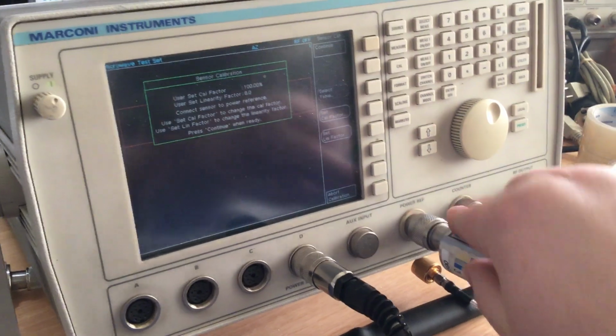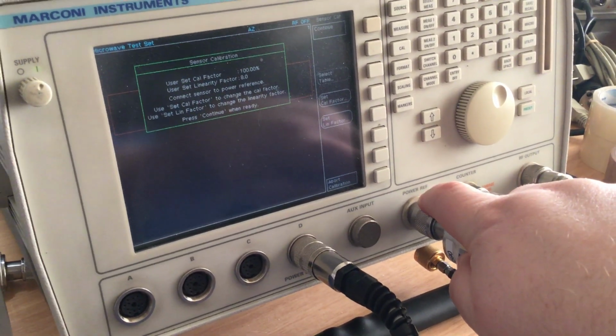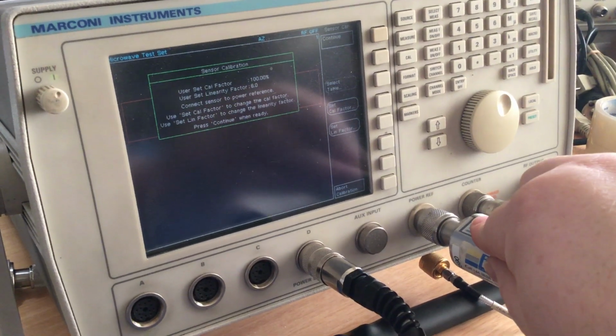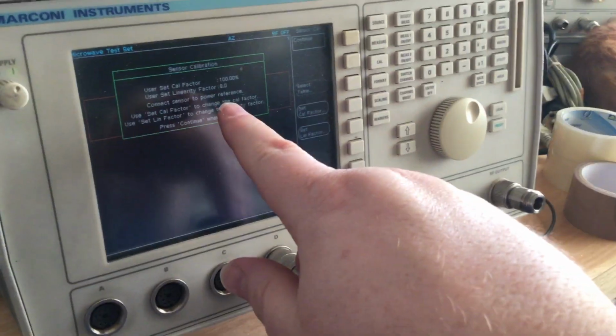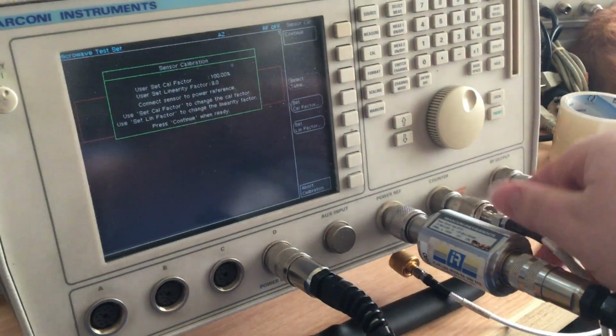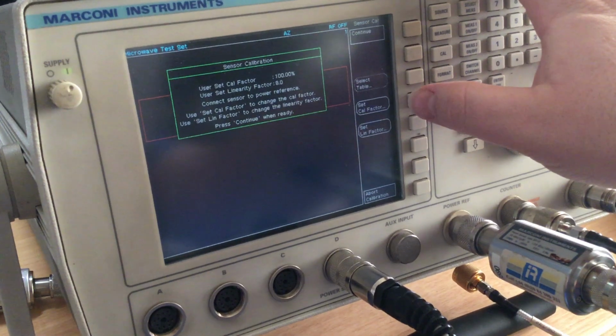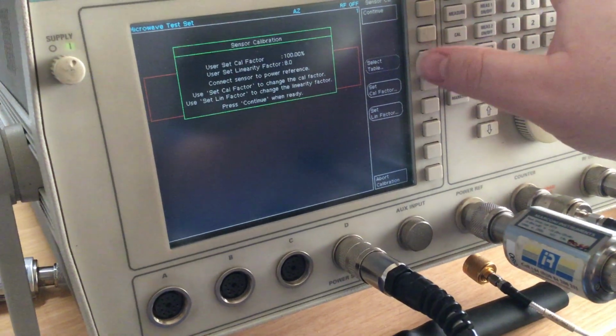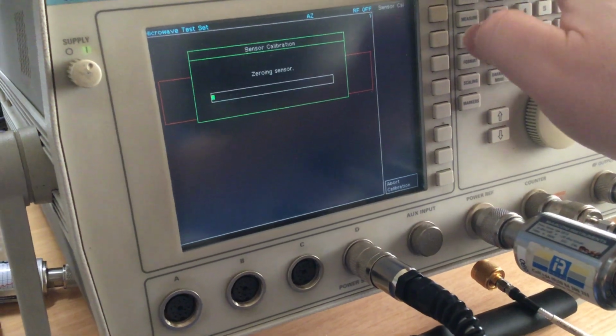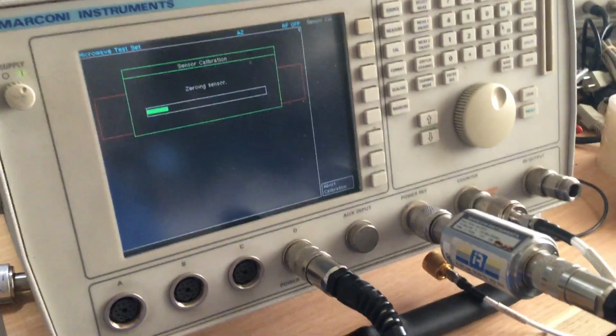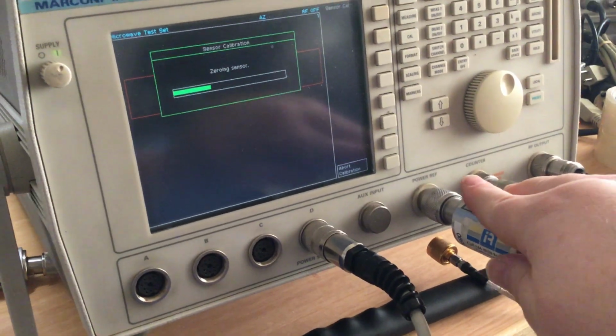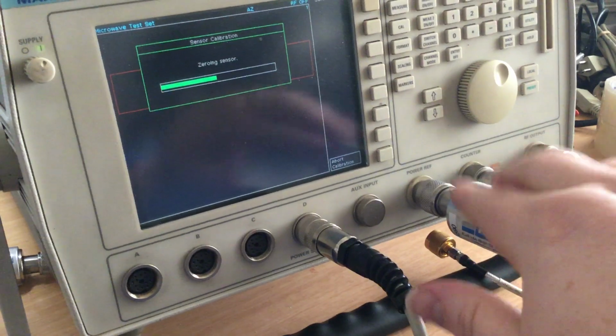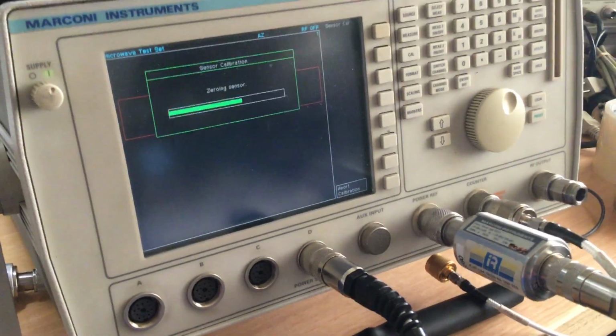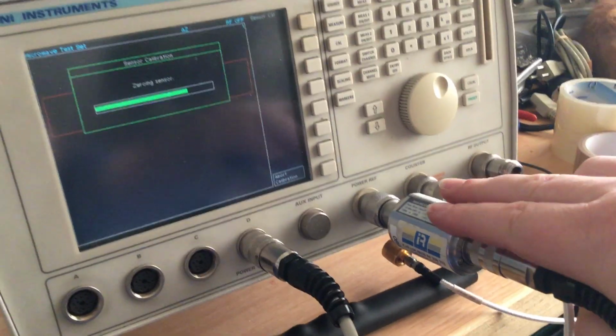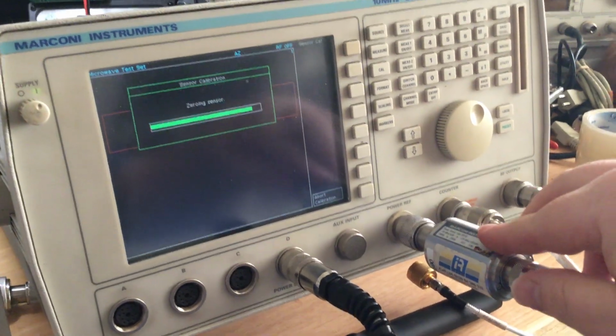So we connected it to the calibration port. This gives 50 megs out at 0 dBm, and that's a reference that this sensor's calibrated against. So we're using the calibration table that's already held within the memory, which represents this sensor, all the linearity data, and now we're going to do continue, and now it's going to zero the sensor, and then it will put 50 megs on at 0 dBm as the next step, and it will then calibrate the instrument against the detector. And that means then that when we've done that, we can move the detector from the reference port to the signal output, and we can go into the instrument calibrations menu and see whether it can self-calibrate.